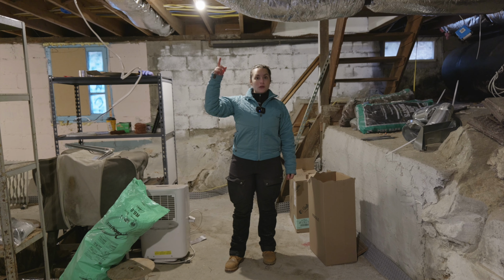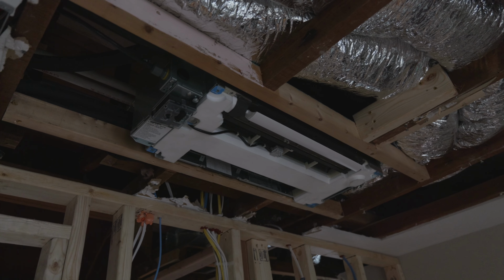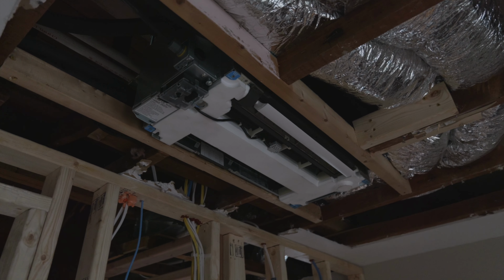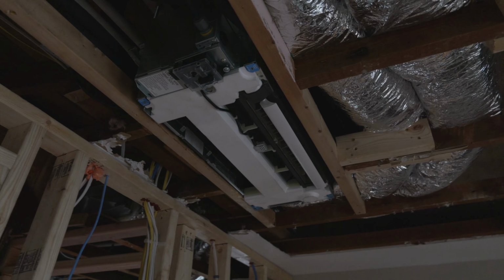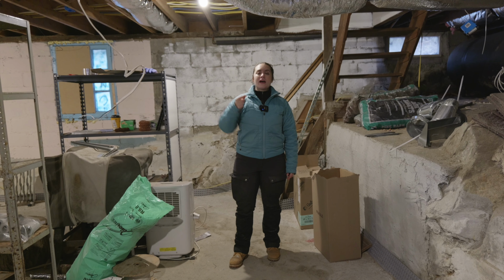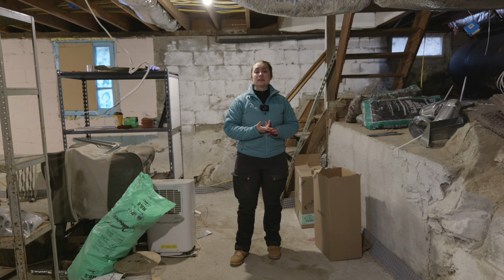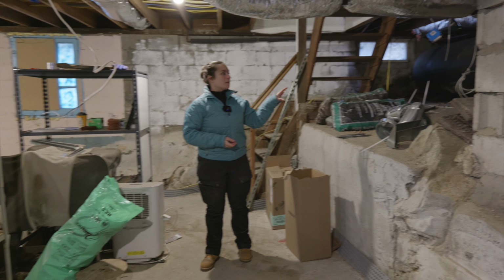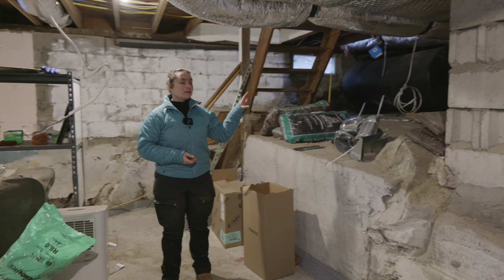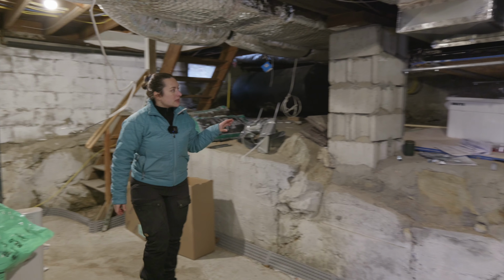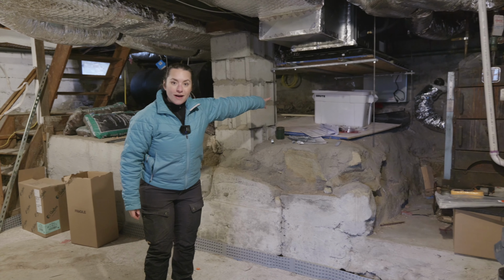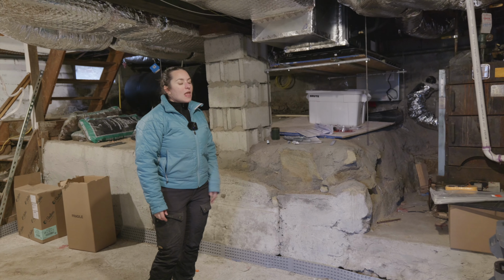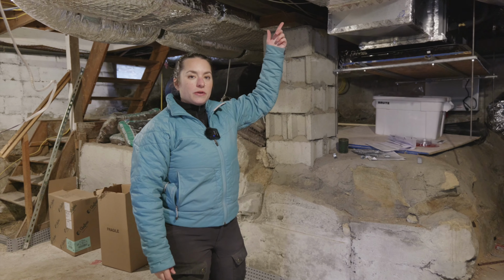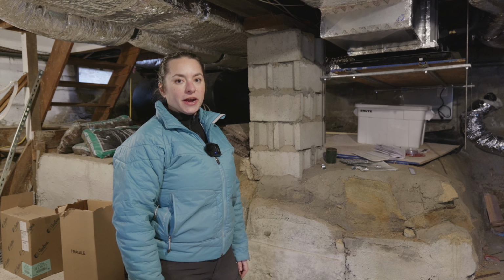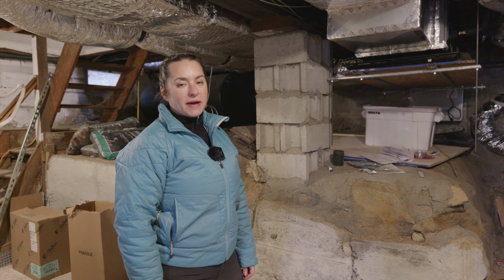The upstairs floors have ceiling cassettes for mini splits, and fresh air will be provided by the upstairs ERV. So we'll have 2 ERV systems: one down here in the basement supplying fresh air to the first floor, which is already in place over there in the back, and another upstairs providing fresh air to the upper floors and bedrooms.